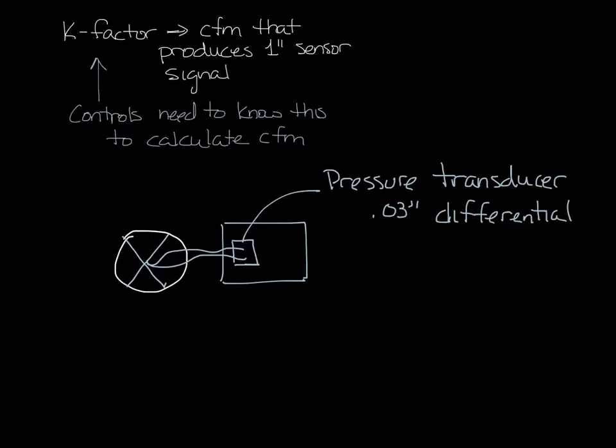When manufacturers design airflow sensors, we want to make the amplification of the sensor high so that a lower CFM will still meet the 0.03 inches of pressure requirement. This is basically done by creating a depressed static pressure reading on the sensor.